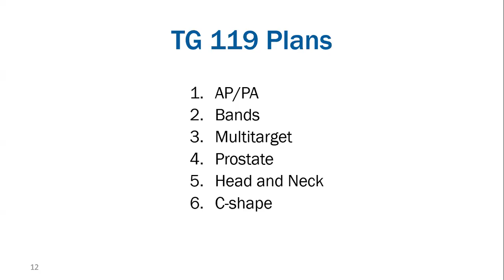Yeah, so the APPA plan is essentially a 10 by 10 square field defined by the jaws where we deliver 200 centigray at mid-plane, the central axis point dose, to calibrate the chamber reading for subsequent tests, and the gamma analysis for film in the central plane.